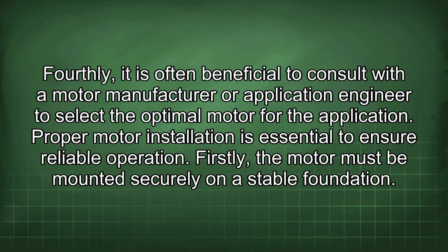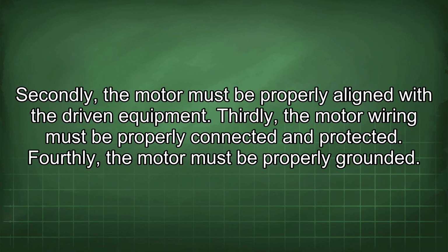Proper motor installation is essential to ensure reliable operation. Firstly, the motor must be mounted securely on a stable foundation. Secondly, the motor must be properly aligned with the driven equipment. Thirdly, the motor wiring must be properly connected and protected. Fourthly, the motor must be properly grounded.